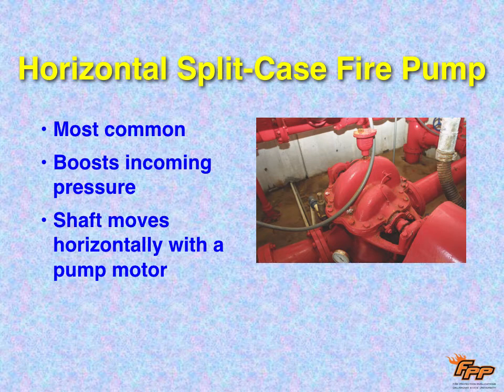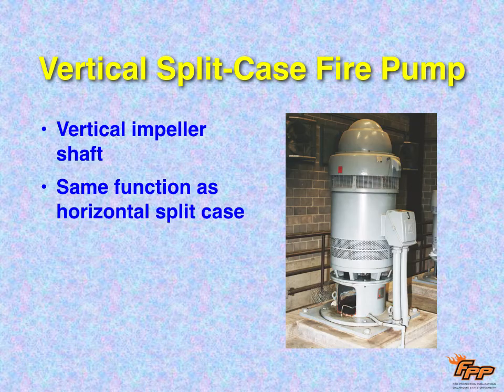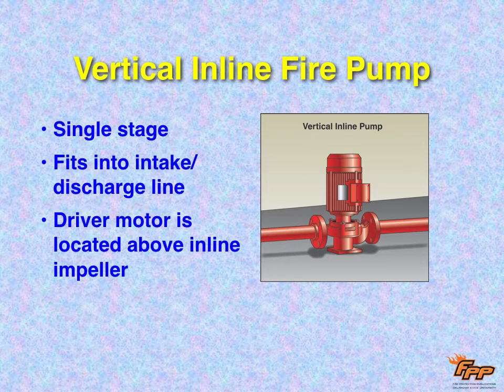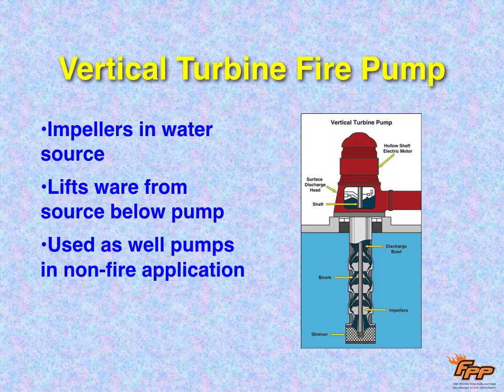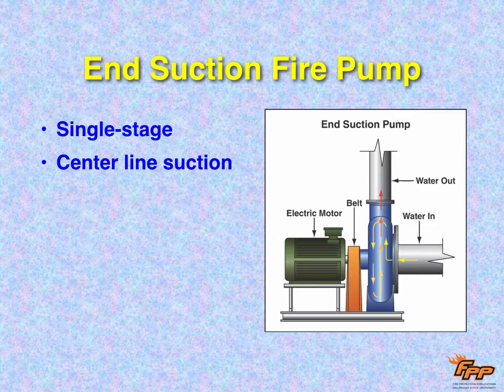Here's a horizontal split case fire pump. This is probably the most common. The shaft's going to move horizontally with the pump motor, and it's going to pick up the pressure and push it up to the higher floors. There are vertical split case fire pumps, which are similar, but now it's vertical instead of horizontal. You can also have vertical inline fire pumps, where these inline pumps boost it as it goes up in elevation, and vertical turbine fire pumps. End suction fire pumps, where it pulls the water.